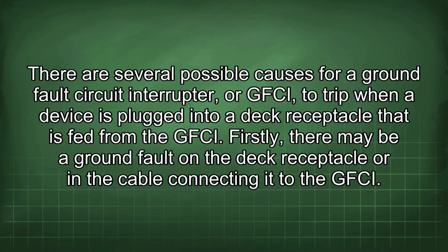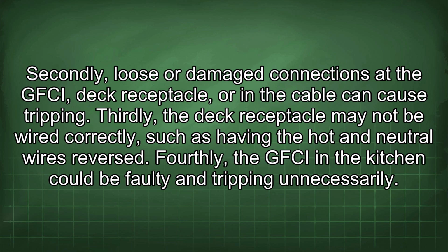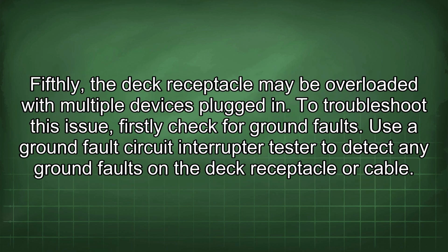There are several possible causes for a ground fault circuit interrupter, or GFCI, to trip when a device is plugged into a deck receptacle that is fed from the GFCI. Firstly, there may be a ground fault in the deck receptacle or in the cable connecting it to the GFCI. Secondly, loose or damaged connections at the GFCI, deck receptacle, or in the cable can cause tripping. Thirdly, the deck receptacle may not be wired correctly, such as having the hot and neutral wires reversed. Fourthly, the GFCI in the kitchen could be faulty and tripping unnecessarily. Fifthly, the deck receptacle may be overloaded with multiple devices plugged in.